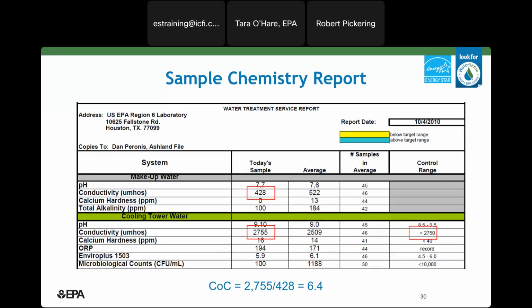Dividing the blowdown conductivity by the makeup conductivity gives us a little over 6 cycles, which really isn't that bad. One other thing to be aware of: where does your conductivity sit with respect to the control point? So you can see on the right, the control point is 2,750. And in this case, the conductivity of the tower is at 2,755. So right at this upper limit, which is where you want it to be.